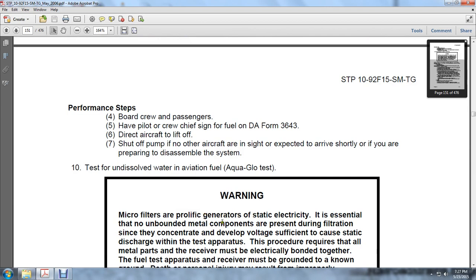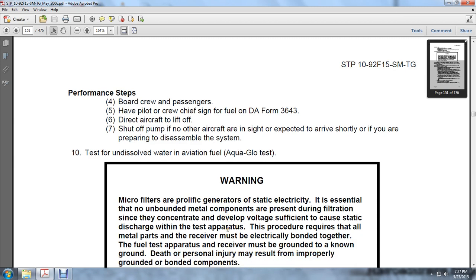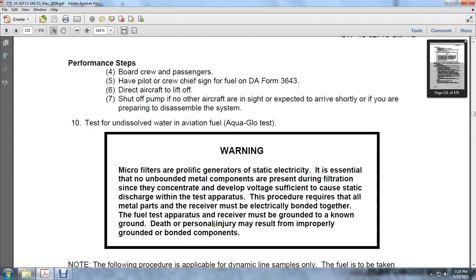Filtration can generate static electricity. It is essential to ensure no unbonded metal components are present during the filtration, since the concentrated developed voltage is sufficient to cause a static discharge within the test apparatus. Procedures require that the metal parts and receivers be electrically bonded together with the fuel apparatus. The receiver must be grounded to a known ground. Death and personnel injury may result from improper grounding of the components.